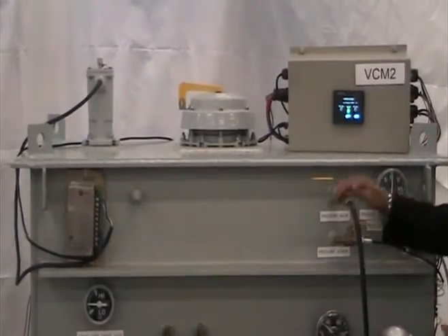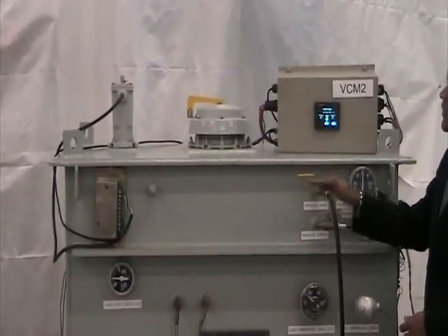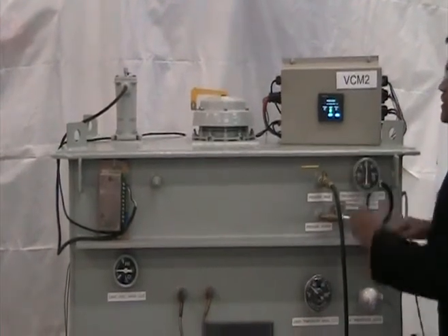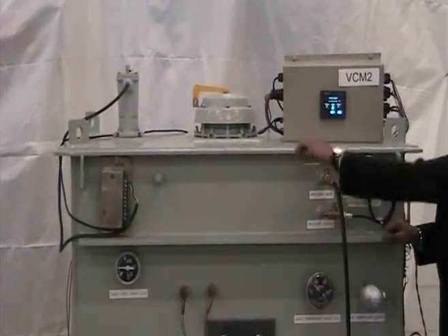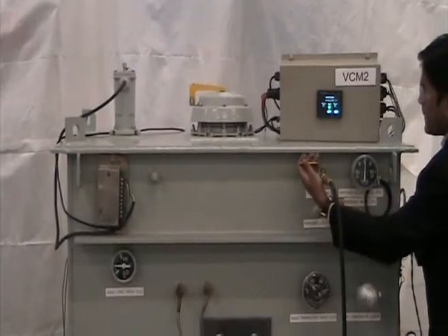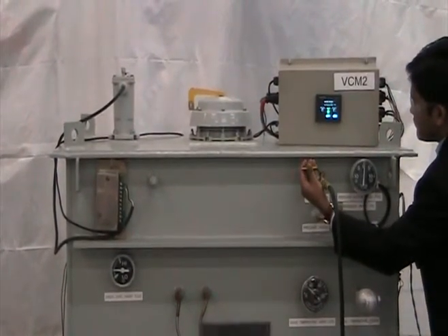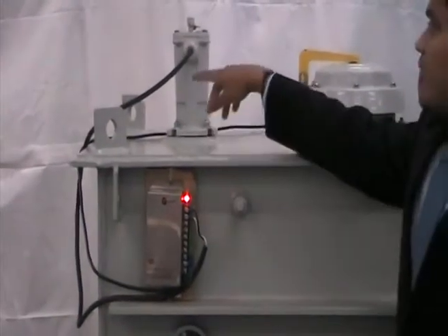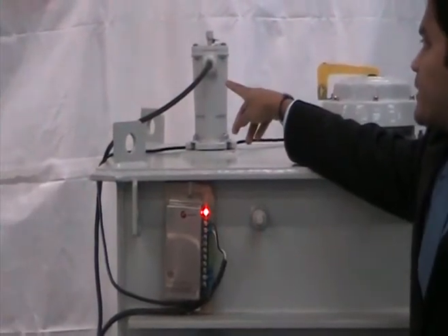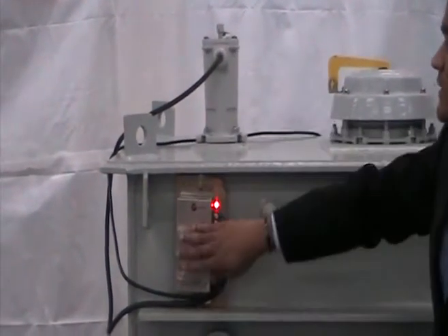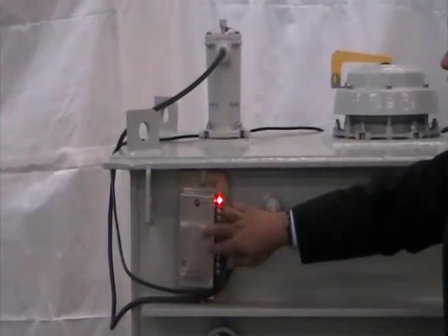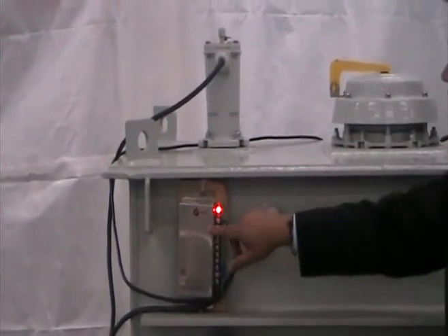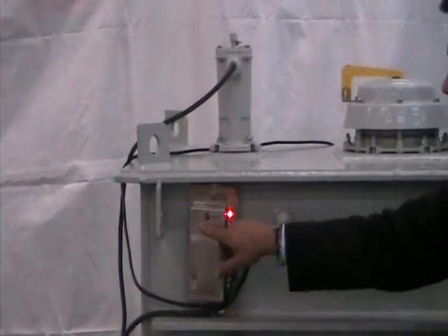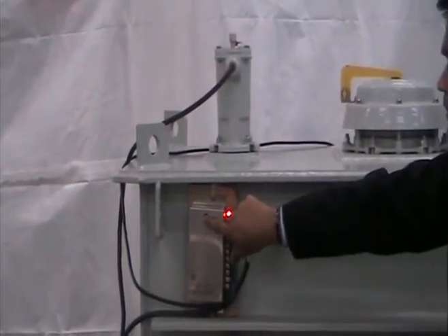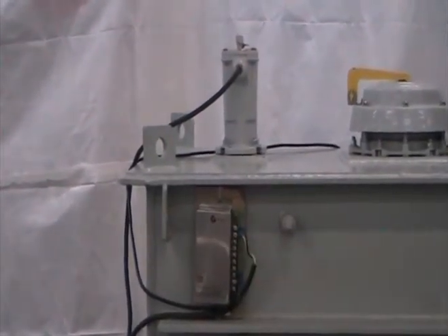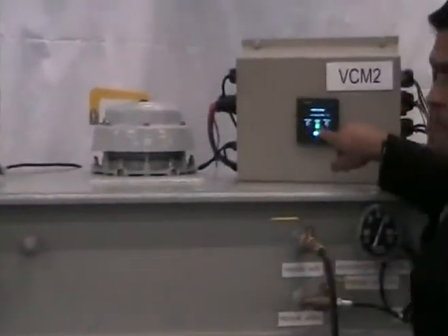Now I will simulate the change in pressure to more than 2 psi per second to activate the SPR using this air hose. You can see when the SPR is activated, the SPR action is latched by sealing relay and the sealing relay is activated. So once the sealing relay is activated, it needs to be reset using this button. Similarly, you need to reset using this button here.